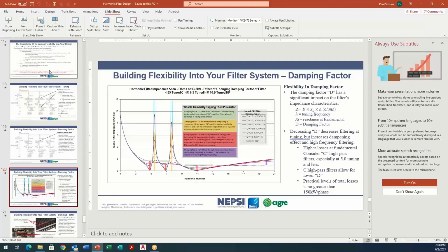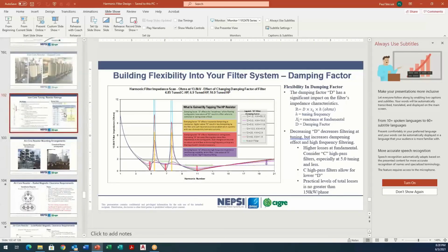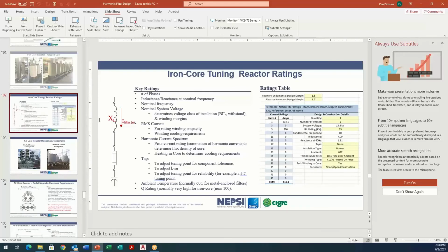So from our standpoint, when we are conservative, we are typically choosing current flow into the filter at each and every frequency to be significantly more than what is predicted by an analysis. And then we're also looking at the fundamental. We're multiplying that times 1.5 for the reactor design alone, not for the capacitor, only for the reactor. What's key here is that I often employ a concept of, is it a 100% rated reactor? Is it a 50% rated reactor? And in this case, my fifth harmonic current, you can see here, is almost equal to the fundamental. So I would call that a 100% rated reactor, and that would be what I would consider a conservative design.